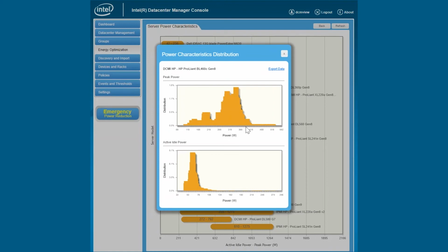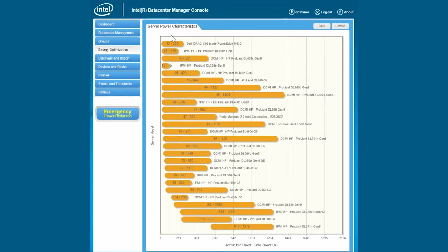Nameplate of the device presents to the user the expected power consumption when the device is fully utilized with all the hardware inside it. So sometimes you don't buy all the disks, and sometimes you don't install all the memory DIMMs, and this will give you a much deeper analysis of the power consumption for every model of device you have in the environment. Let's see some more capabilities.